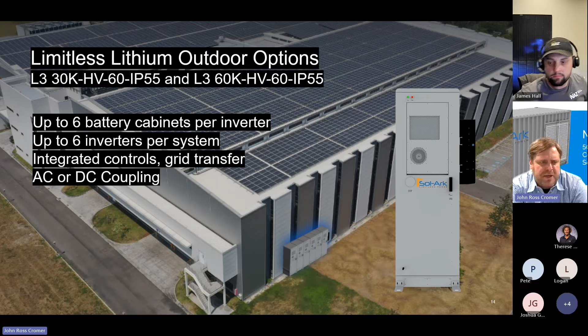And the reason for that is that we have a containerized outdoor solution coming to market in the second half of 2024. By the time you get more than 6 inverters and 6 battery cabinets per inverter, you might as well go into the containerized solution. Inside, in a more controlled environment, in an authorized personnel only room, you might have a little bit more bussing to do to get into those larger system sizes. Outside, doing 6 inverters in parallel and 6 battery cabinets per inverter is very, very easy to wire. So it's a very easy system to design and install and implement. And if you got any larger than that, that's when you would go into our shipping container solution.